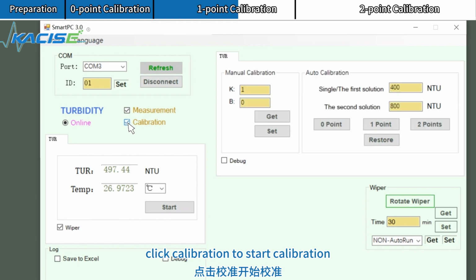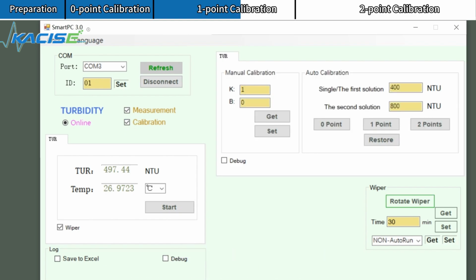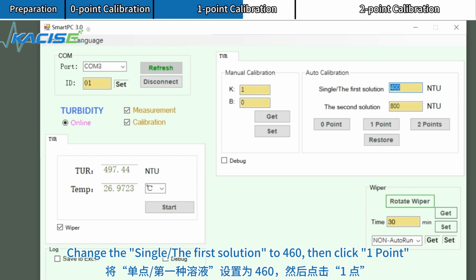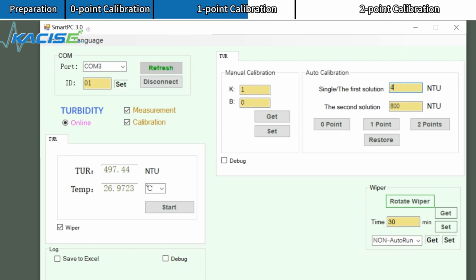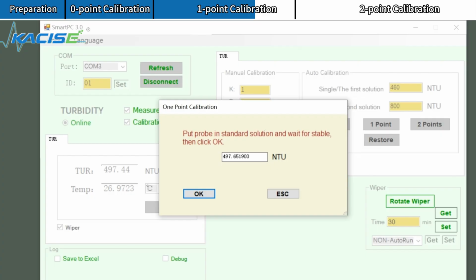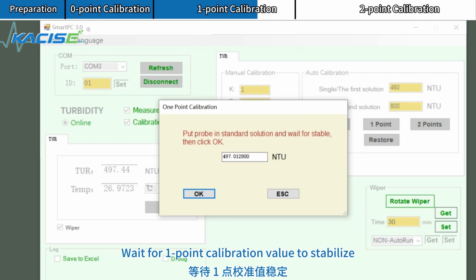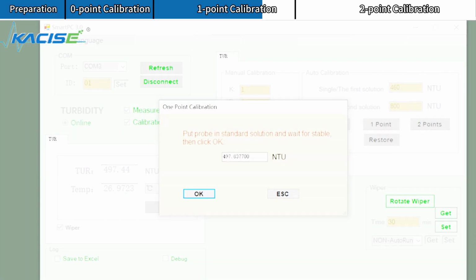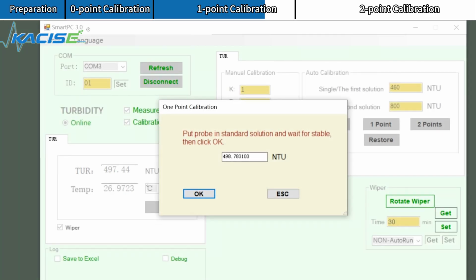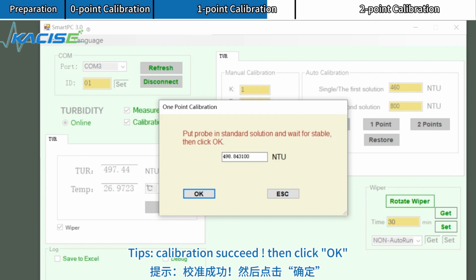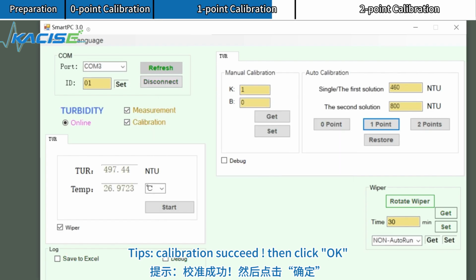Click Calibration to start calibration. Change the first solution to 460. Then click 1 point. Wait for 1 point calibration value to stabilize. Calibration value stabilized. Click OK. Tips: calibration succeed. Then click OK.